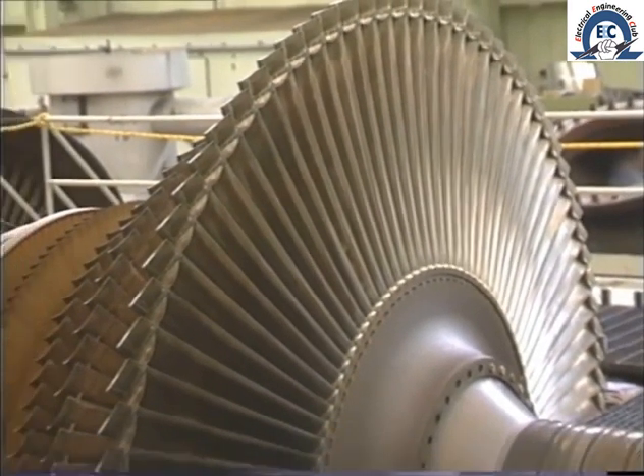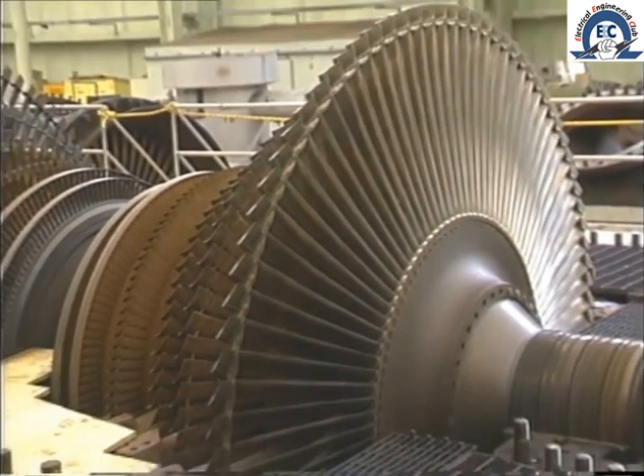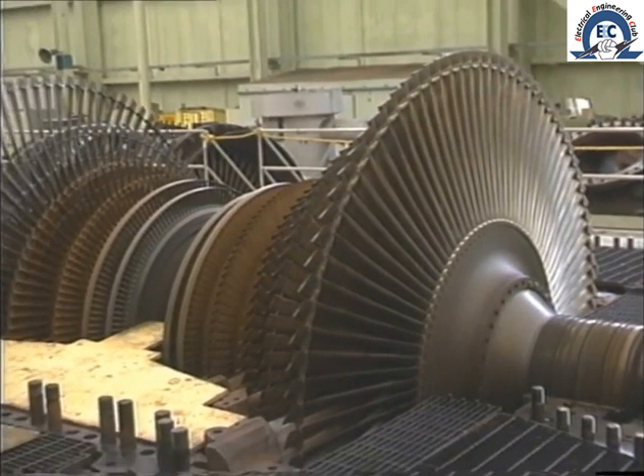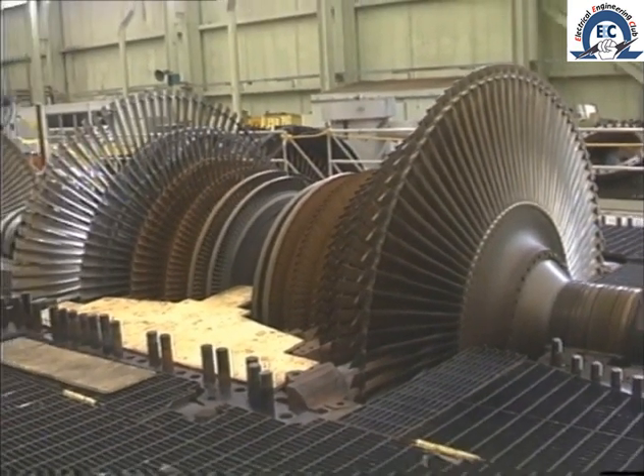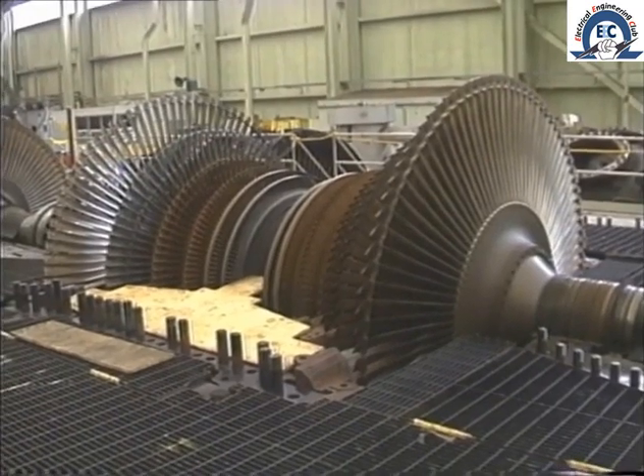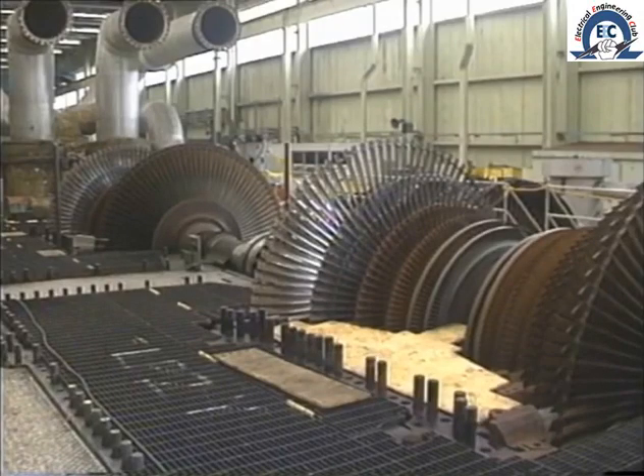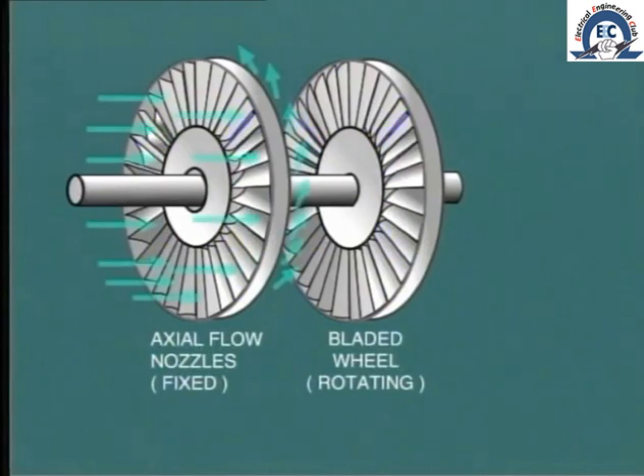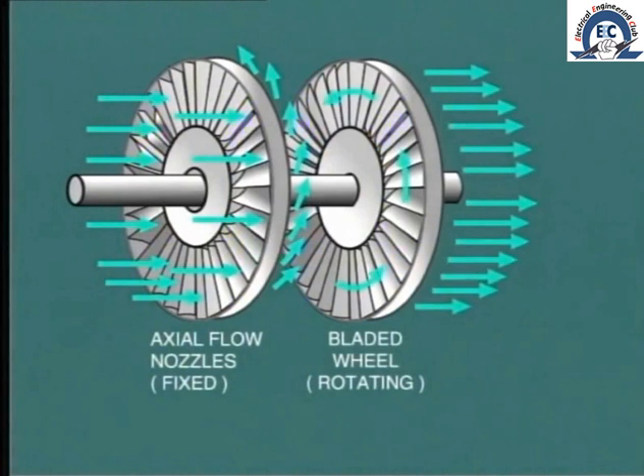The simple answer is that the turbine blades are designed to take advantage of the decrease in steam pressure and consequent increase in steam velocity. The heart of the turbine, the bit that makes it work, is the relationship between the fixed and moving blades. The fixed blades guide the steam onto the moving blades. As the steam passes through the moving blades, it causes the disk to which they are attached to rotate, and consequently the shaft rotates.